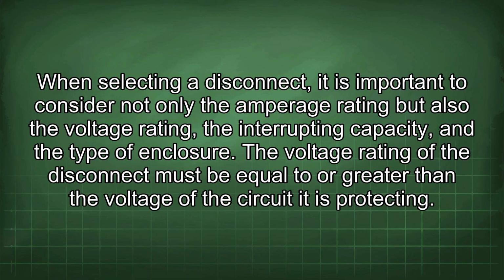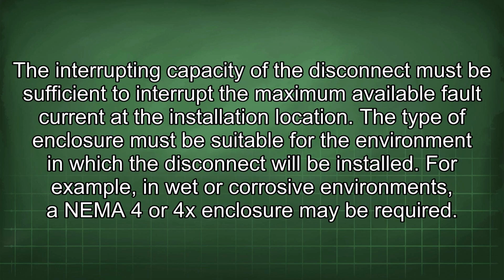When selecting a disconnect, it is important to consider not only the amperage rating but also the voltage rating, the interrupting capacity, and the type of enclosure. The voltage rating of the disconnect must be equal to or greater than the voltage of the circuit it is protecting. The interrupting capacity of the disconnect must be sufficient to interrupt the maximum available fault current at the installation location. The type of enclosure must be suitable for the environment in which the disconnect will be installed. For example, in wet or corrosive environments, a NEMA 4 or 4X enclosure may be required.